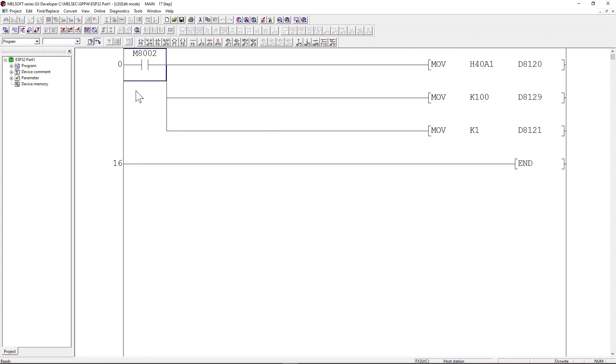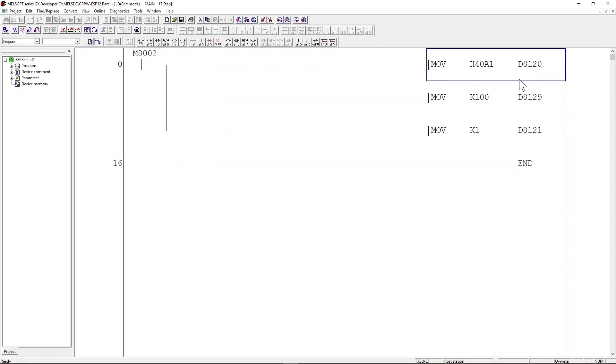First, we load the M8002 PLC register, which is a special register that only turns on when the PLC is powered up. Upon power on, we will move the value of 40A1 hex into the PLC D8120 register.